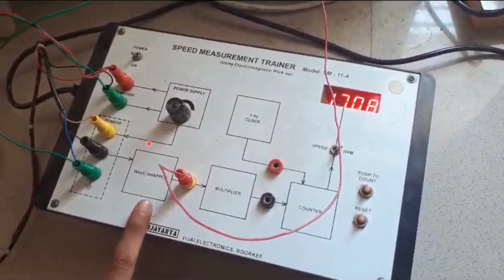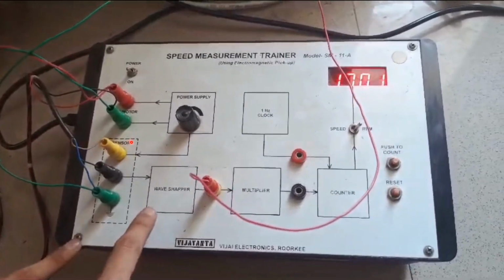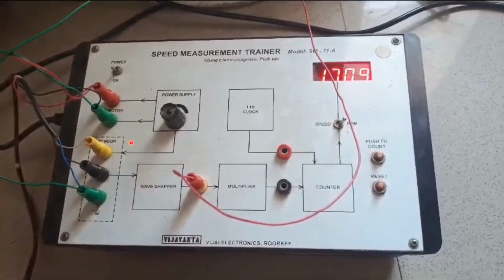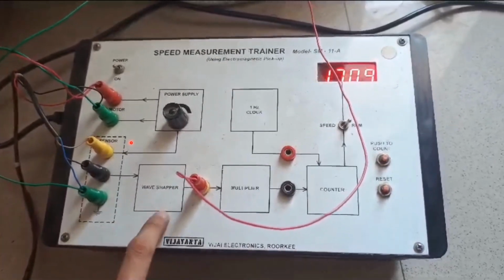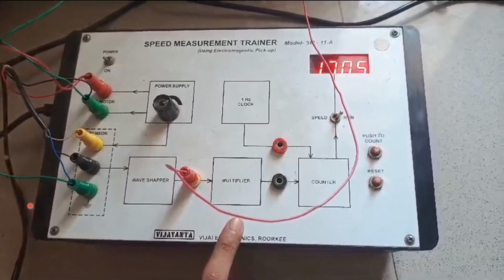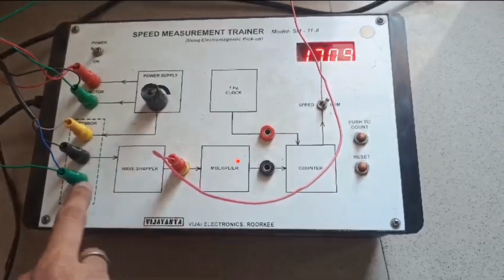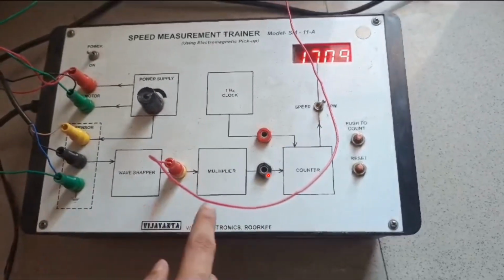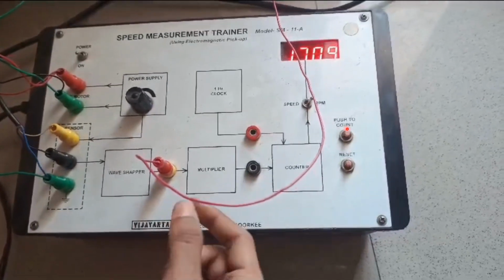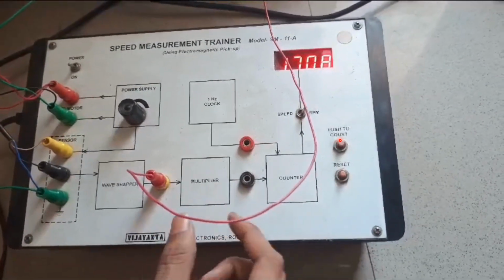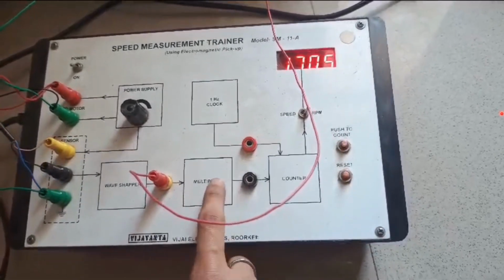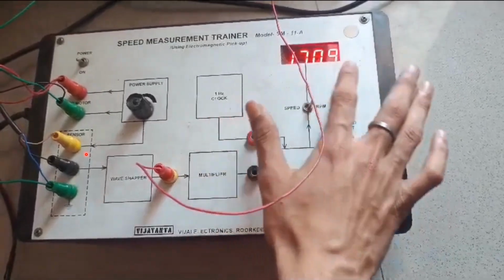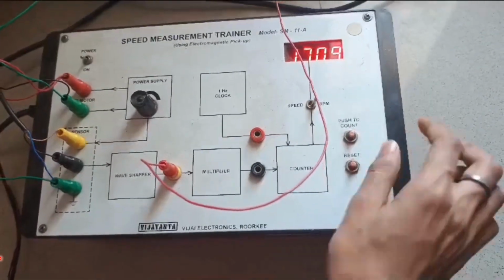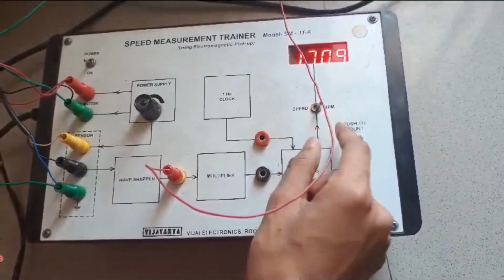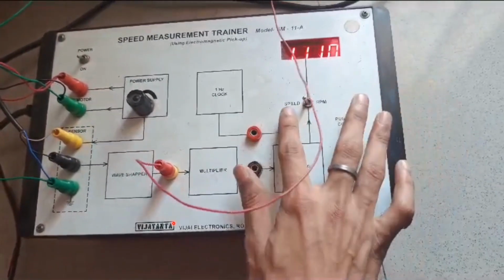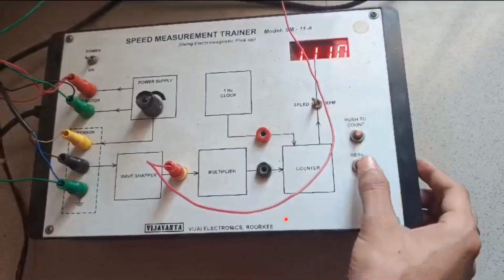Basically, how does the MPU sensor sense the readings? When a ferrous material comes in very close proximity to the MPU sensor, there is a disruption in the magnetic field lines. But at the very next moment, when there is an air gap, there is no disruption in the magnetic field. So this change in the magnetic field lines induces voltage in the coil wound around the soft iron core inside the MPU sensor. That feeble induced AC voltage is then sent to the wave shaper, which removes the unwanted noise, and is then sent to the multiplier, and then to the counter.